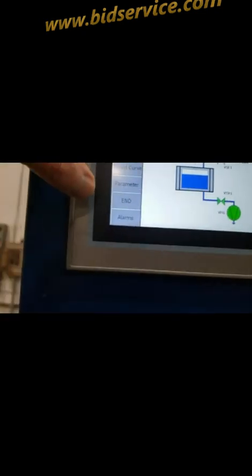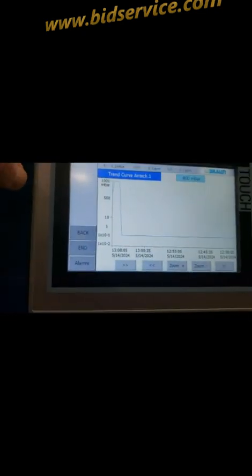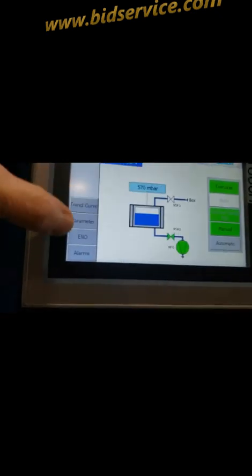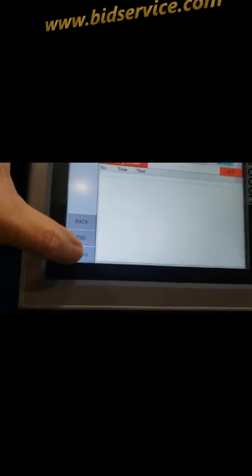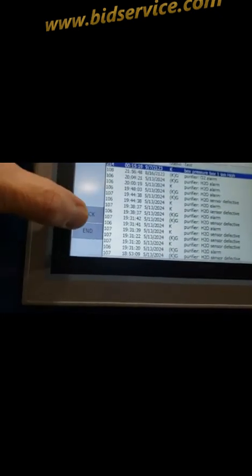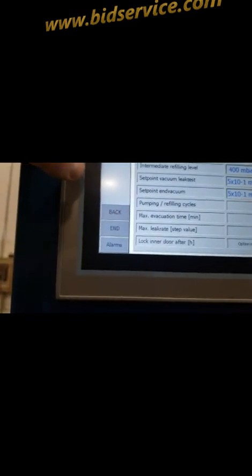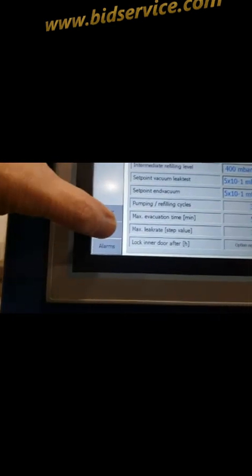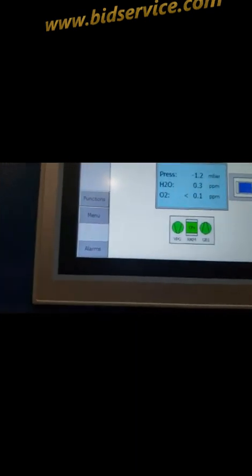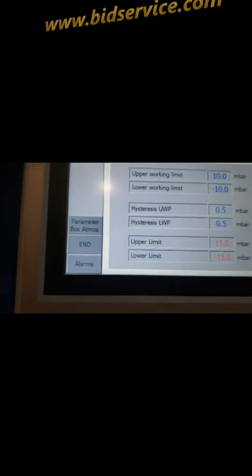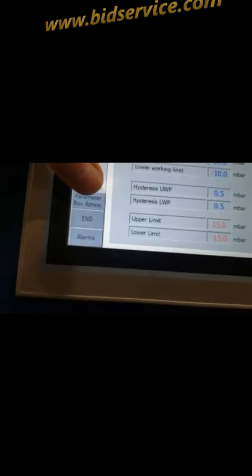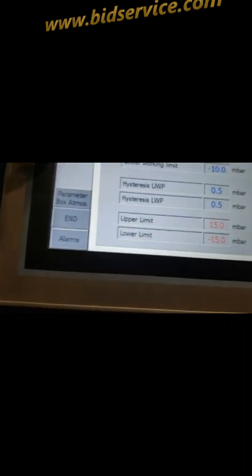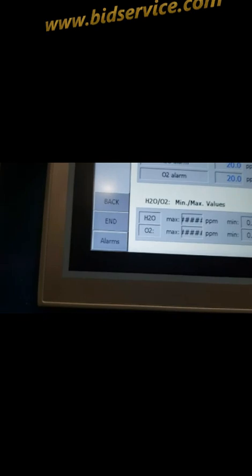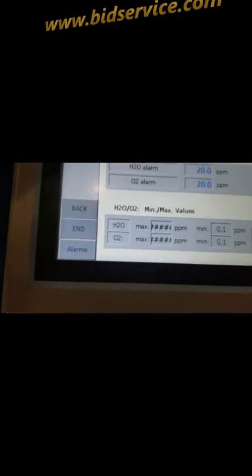So while that's pumping out, we'll just show you a few other things here. There's your trend curve. If there are any alarms, they'll come up here. That'll show you a history of the alarms. And here, parameters we went through, that's for your auto pump out and refill. There are a few other things you can do from the screen. You can hit the box here. You can set your upper and lower working limits, as well as your hysteresis and your upper and lower limit of the box. You can set your alarm limits for your H2O alarm and O2 alarms.